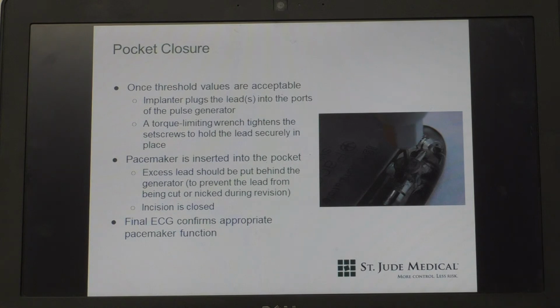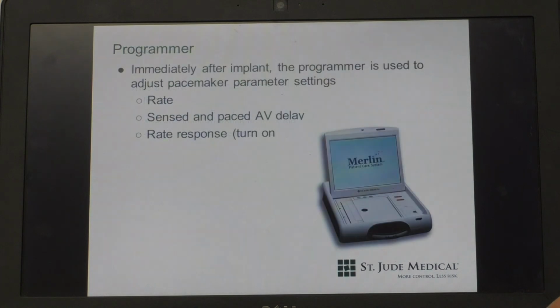So once everything is acceptable, the leads are in a good position, we open up the pacemaker and it's inserted into the pocket. Well, before that, you plug in the right atrial and right ventricular leads, and use the hex wrench, and you screw it in. And then the pacemaker is put in the pocket. And then with St. Jude, we have Bluetooth in our pacemaker, so we can check everything right away, that everything's in the right position, the thresholds still look good. And that's it. So then we speak to the doctor and we talk about programming. What's the base rate you want? What AV delays do you want? And then we program accordingly. Do you want rate response on, rate response for chronotropic incompetence, that type of thing.